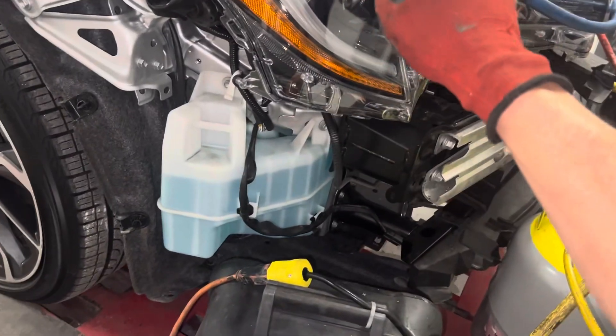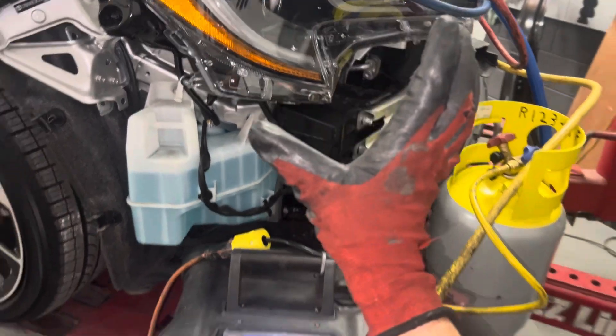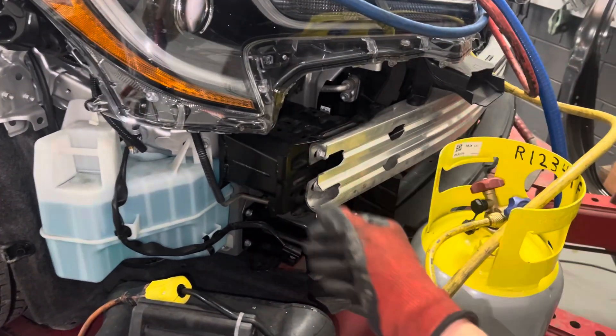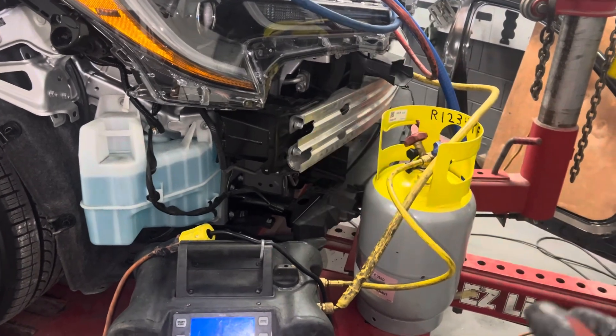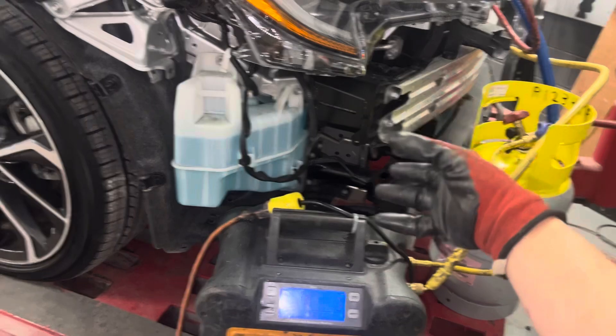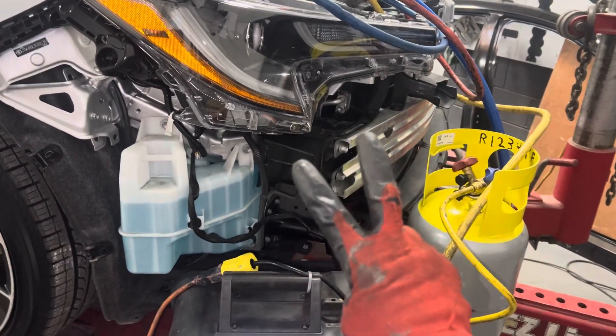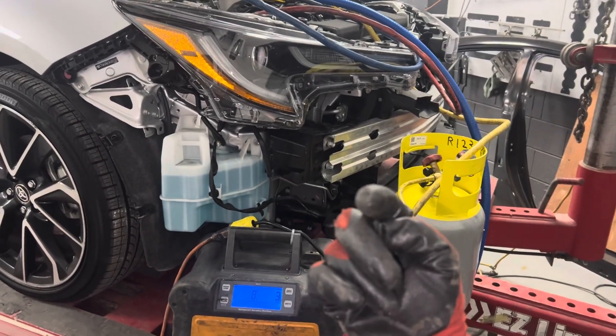You can do it all in one procedure: recovery, evacuate, and recharge — without separating it into two different days like a repair. A repair is different: the system is damaged but full of refrigerant, so you need labor to recover it, then disconnect, come back several days later when the system is together, hook back up to the equipment a second time, and go through evacuate and recharge. Two different separate operations, two different separate charges. Hope somebody learned something — see you later, ask questions in the comments.